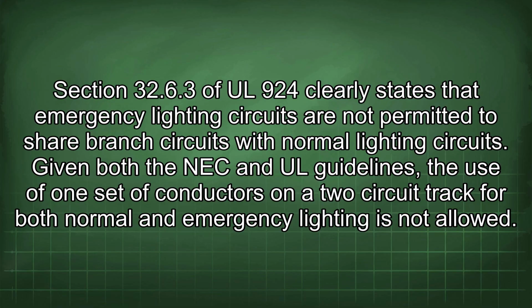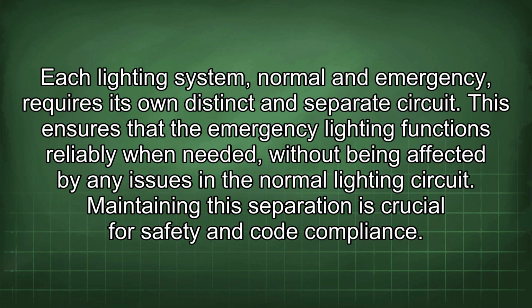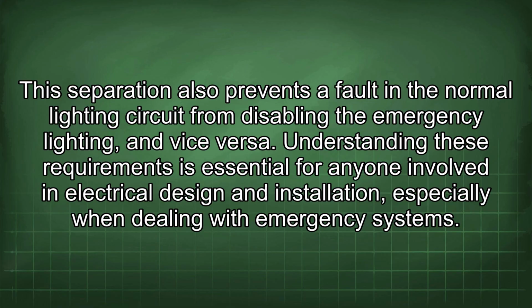normal lighting circuits. Given both the NEC and UL guidelines, the use of one set of conductors on a 2-circuit track for both normal and emergency lighting is not allowed. Each lighting system, normal and emergency, requires its own distinct and separate circuit. This ensures that the emergency lighting functions reliably when needed, without being affected by any issues in the normal lighting circuit. Maintaining this separation is crucial for safety and code compliance. This separation also prevents a fault in the normal lighting circuit from disabling the emergency lighting, and vice versa.